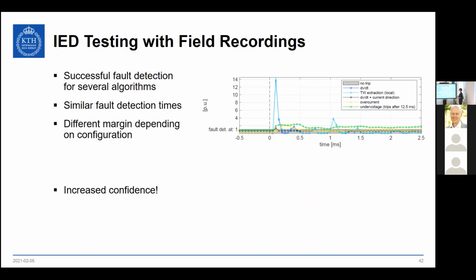To give you an idea, here are the fault detection algorithms normalized to thresholds. The trip happens at 1 down here, and at time 0 the fault happens. We can see how different algorithms cross the threshold with different margins. Again, this complements the systematic real-time testing and further increases confidence in the previously developed ideas and solutions.